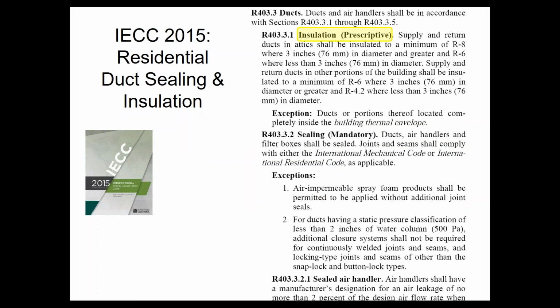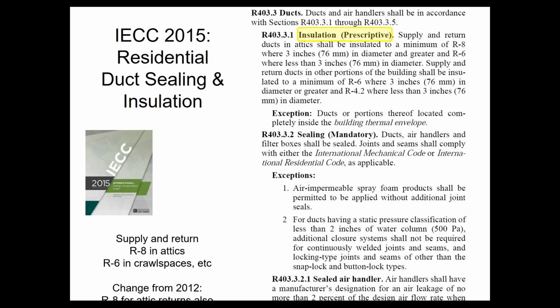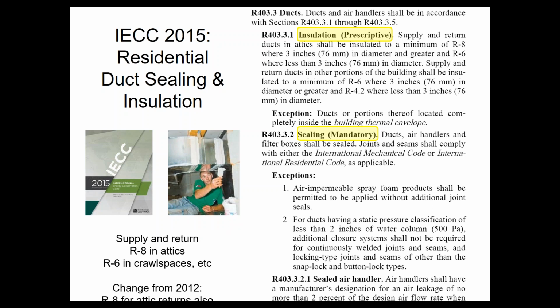Ductwork residentially has to be sealed and it has to be insulated. Insulation for both supply and returns needs to be R8 in the attics, R6 in the crawl spaces. The big change there from the previous version of the code is that it used to be only R6 in the attic. Now it's up to R8. That's a big deal, but that is a change.